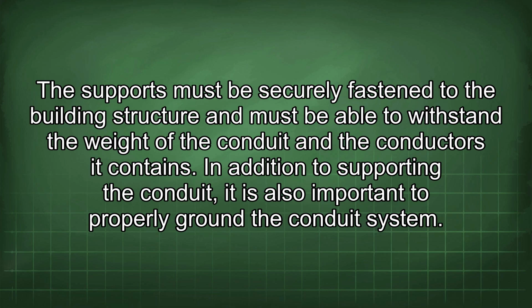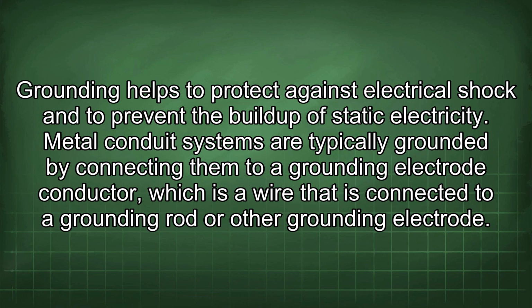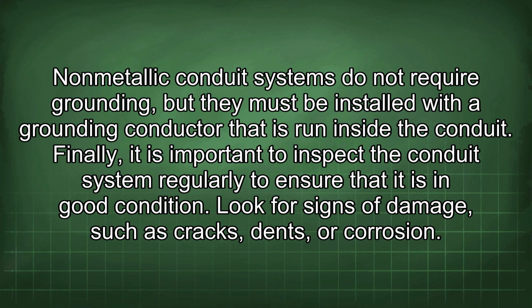In addition to supporting the conduit, it is also important to properly ground the conduit system. Grounding helps to protect against electrical shock and to prevent the buildup of static electricity. Metal conduit systems are typically grounded by connecting them to a grounding electrode conductor, which is a wire that is connected to a grounding rod or other grounding electrode.